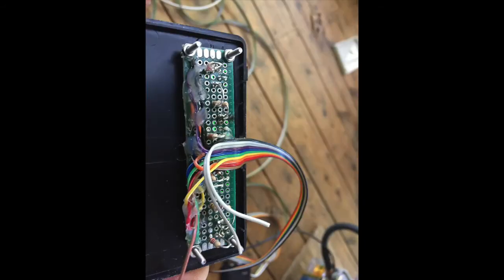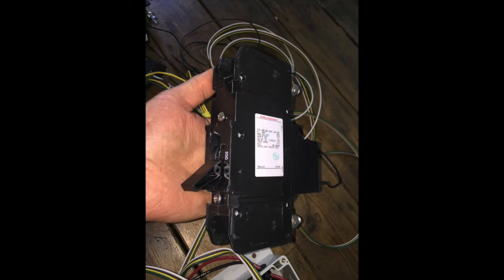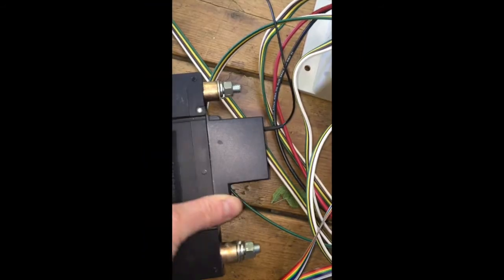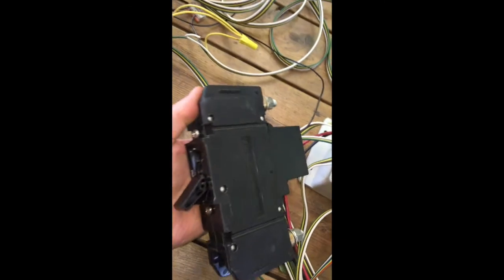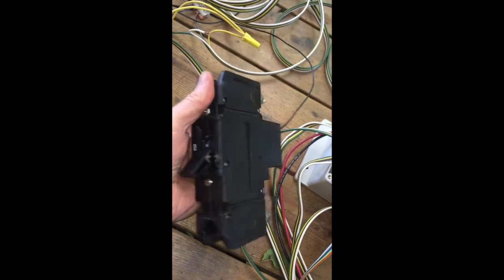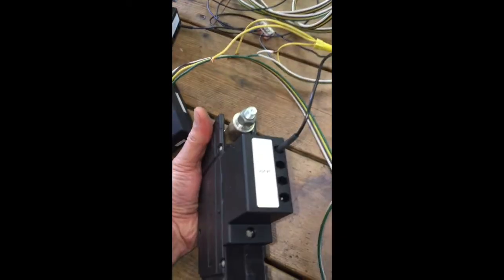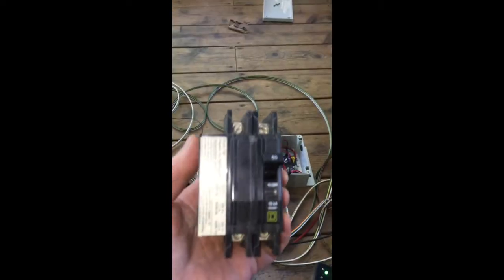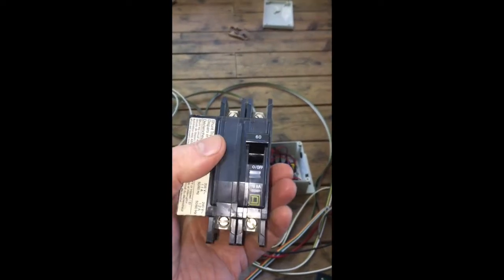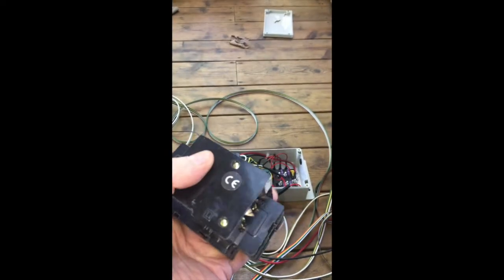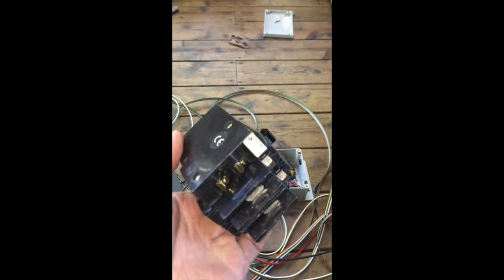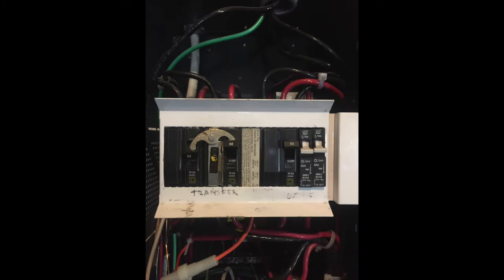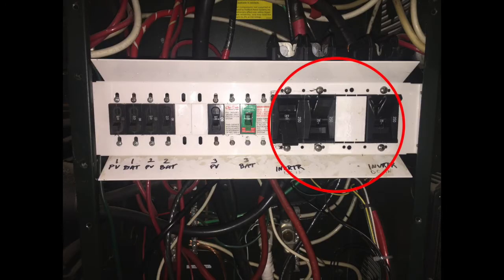I used shunt trip breakers that open when a voltage signal is received. There are 4 of these breakers, one for the solar DC charging, one for the generator AC charging input, and one each for DC power input to the 2 inverters. These are all what I'd consider redundant fail-safe systems except for the generator charging breaker. Because I can't set the inverter to a low enough voltage for the batteries, the BMS is set to open the AC charging input breaker when the batteries achieve their charged set point.